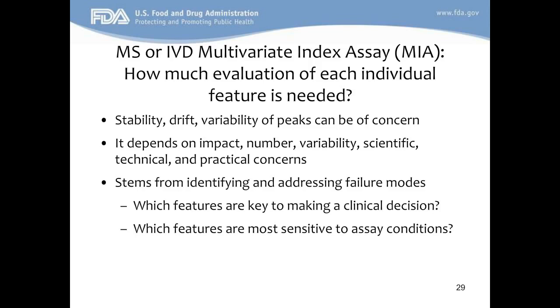Obviously, with any individual peak, and certainly with multiple peaks, the variability of the peak is a concern. I think probably the most important part of this slide is the last bullet point here. When it comes to understanding which peaks are most important and how much evaluation of each individual feature is needed, a developer or manufacturer should ask which features are key to making the clinical decision. Those are the features that need to be understood in the most detail from an analytical performance standpoint. And then of those features that are key to making a clinical decision, which are most sensitive to the assay conditions, and which assay conditions are most affecting the variability in the detection and quantitation of those peaks.